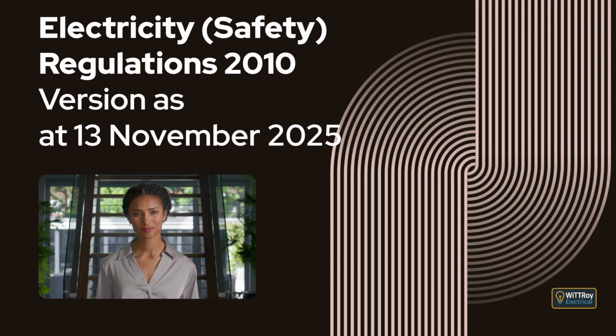Reg 73A Before connecting installations to power supply. This regulation explains that before connecting a low or extra low voltage installation or part installation to a power supply, the person making the connection must be satisfied that the installation is safe to connect, that all required testing has been done, and that any required certificate of compliance has been issued or sighted within the previous 6 months. It also explains that if the work requires inspection, the inspection must be completed and a record of inspection issued or sighted within the previous 6 months, and where required, the certificate of compliance or a copy must be attached to the record of inspection.